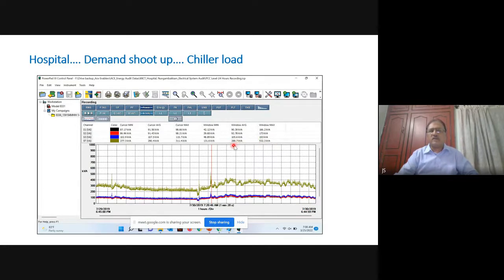So approximately, if you know how to stagger this, or if you use a soft starter or a VFD for the chiller, this is a star delta starting. So we recommended to this hospital to go for a device with which they will be able to reduce the starting KVA demand, so that they will be able to surrender the KVA and reduce the amount of money they are paying on the demand charges. So just as an example, like I said, a 24-hour window will always reveal when actually the peak happens.